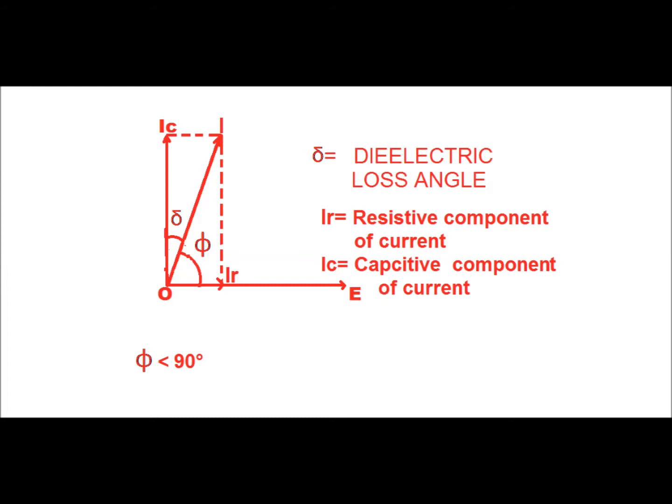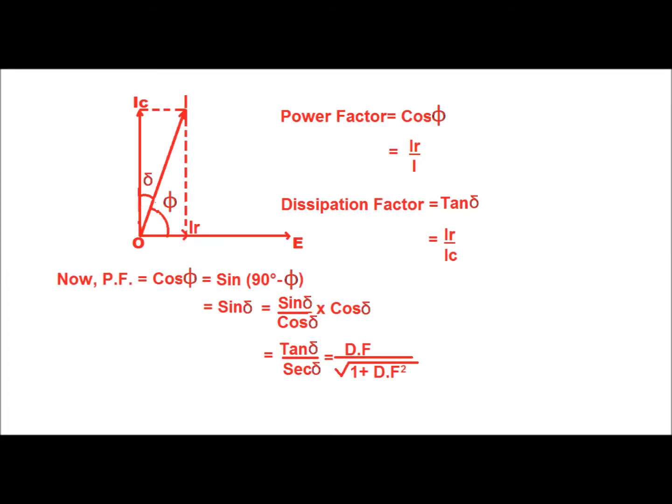In the practical case, the power factor angle phi is not 90 degrees — rather it is less than 90 degrees. The practical diagram has been shown in this figure. In this figure, IR is the resistive component of current, I is the resultant current, and phi is the power factor angle. The delta angle is called the dielectric loss angle. The more the insulator deteriorates, the more the angle delta becomes. From this vector diagram we can see that power factor equals cos phi equals IR divided by I.